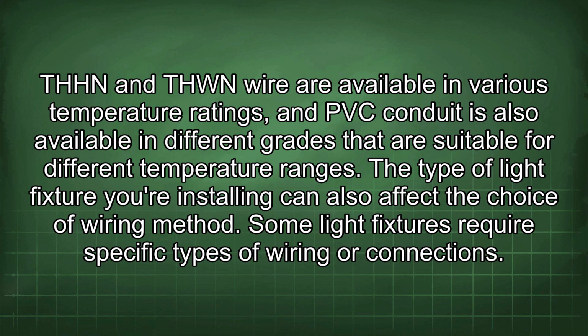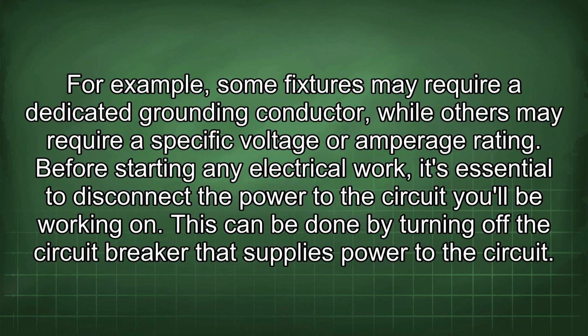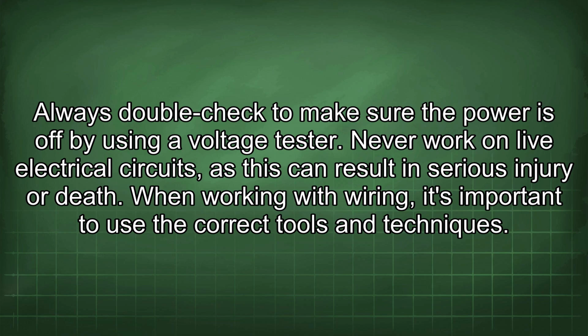The type of light fixture you're installing can also affect the choice of wiring method. Some light fixtures require specific types of wiring or connections. For example, some fixtures may require a dedicated grounding conductor, while others may require a specific voltage or amperage rating. Before starting any electrical work, it's essential to disconnect the power to the circuit you'll be working on. This can be done by turning off the circuit breaker that supplies power to the circuit. Always double check to make sure the power is off by using a voltage tester. Never work on live electrical circuits, as this can result in serious injury or death.